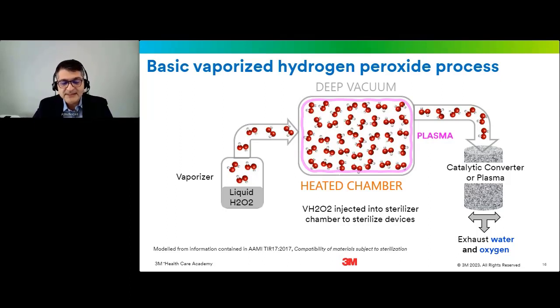The sterilant is decomposing as it kills, and it contacts the items and inside the load, inside the sterilizer chamber. The concentration is diminishing during exposure. So as time passes, the concentration of hydrogen peroxide decreases as well. After the process, the remaining hydrogen peroxide passes through a catalytic converter or a plasma to convert hydrogen peroxide to water and oxygen molecules in order to not have toxic waste at the end.